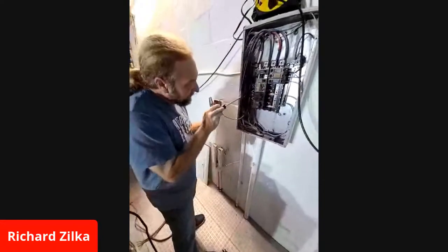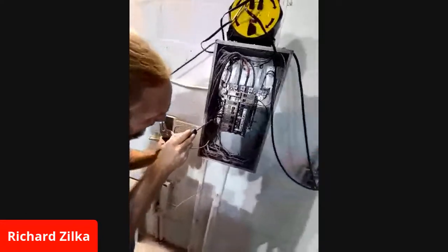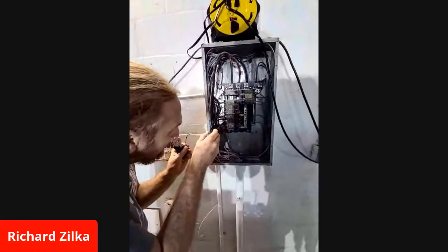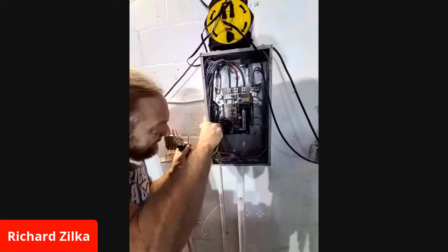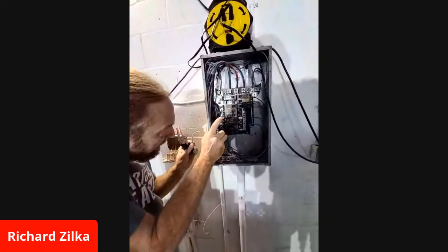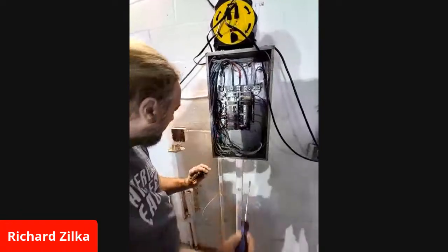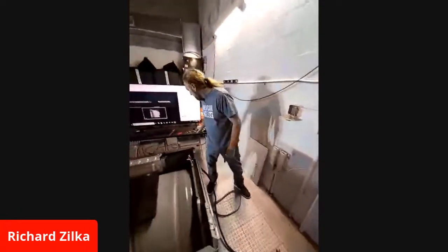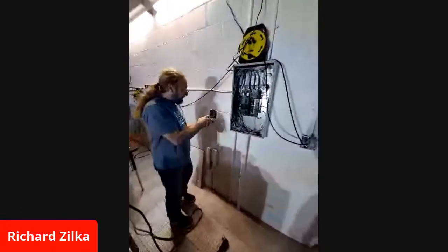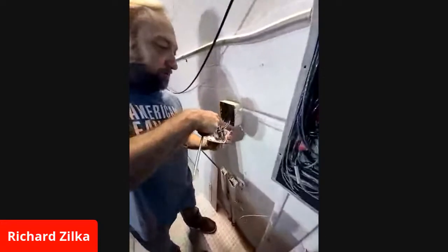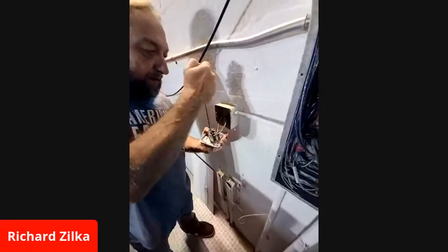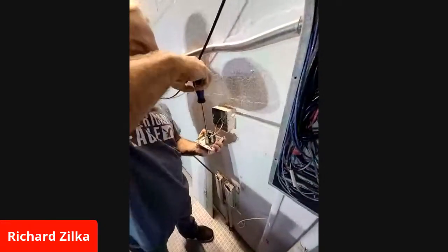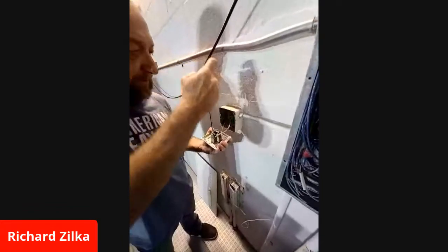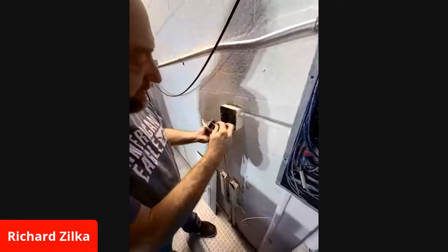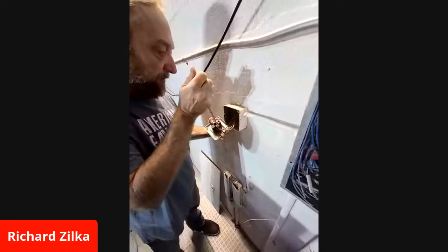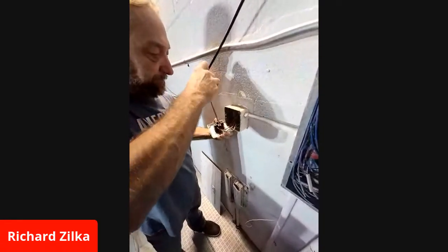I'm going to hook it up over here on this side to one of my neutrals that doesn't have a wire in it, so I'll move this one over to neutral. But before I do, I'm going to move the ground that's on here to the neutral side where we didn't have power, because ground is a safety and we do have to run another wire, but we don't have it here today. I'll move that ground over to the neutral side for testing purposes, and we'll go back and test the dryer out again.